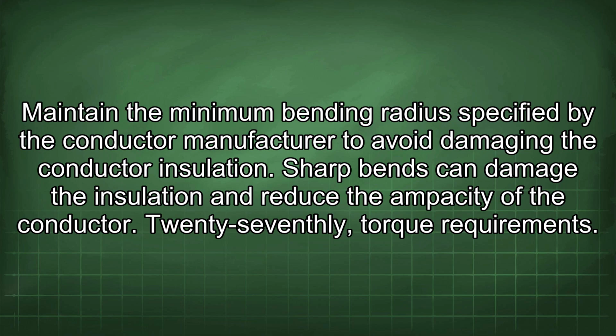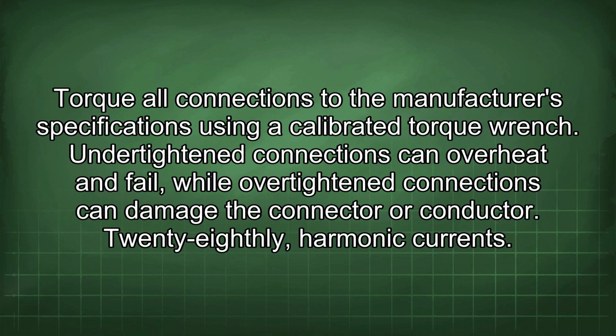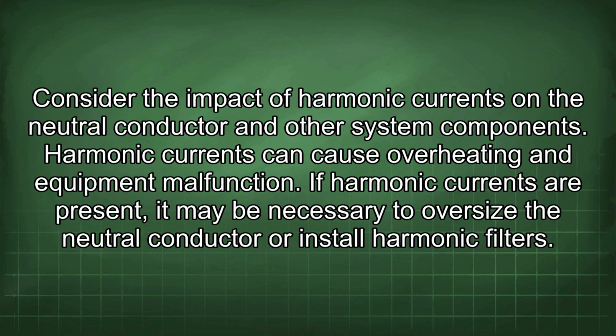27th, torque requirements. Torque all connections to the manufacturer's specifications using a calibrated torque wrench. Under-tightened connections can overheat and fail, while over-tightened connections can damage the connector or conductor. 28th, harmonic currents. Consider the impact of harmonic currents on the neutral conductor and other system components. Harmonic currents can cause overheating and equipment malfunction. If harmonic currents are present, it may be necessary to oversize the neutral conductor or install harmonic filters.